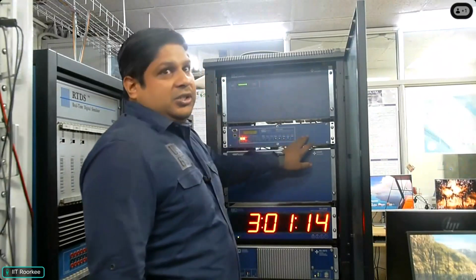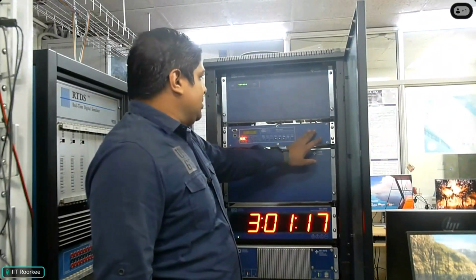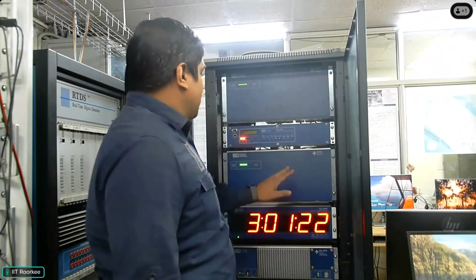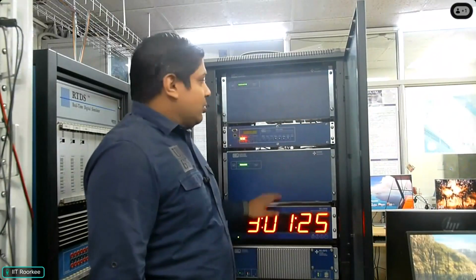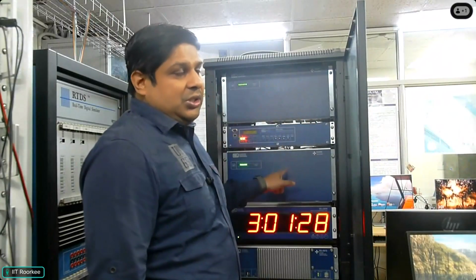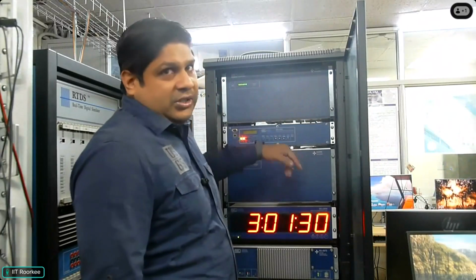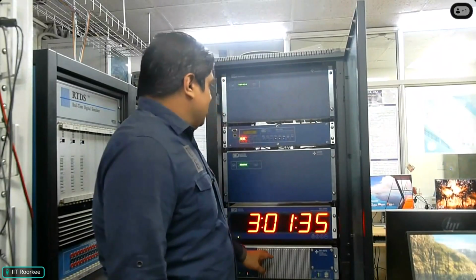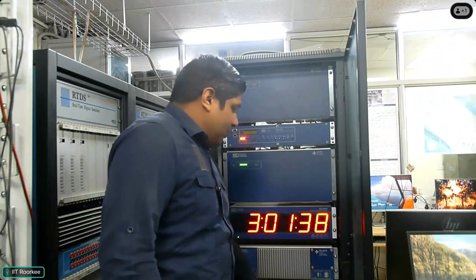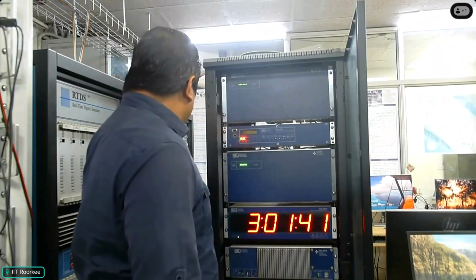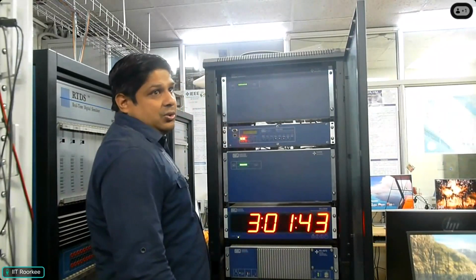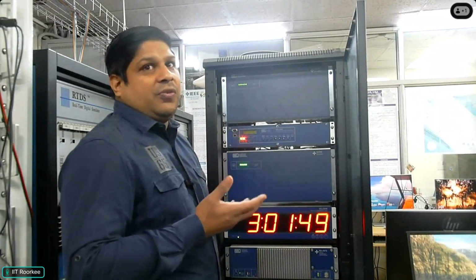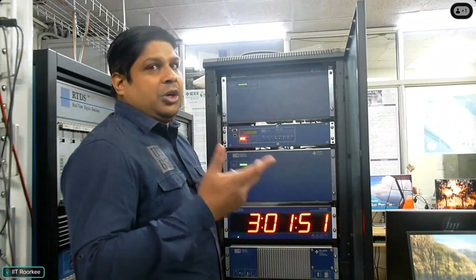And then this is a distance protection relay, a transmission protection relay. This SEL 311C. Most of the devices here are from SEL. And then this is the GPS clock. All these devices are time synchronized using the GPS clock. I will show you the connections at the backside when we go there. And this is the PDC. So all these PMU devices, 3 hardware PMUs here. And here we have a GTNet X2 card also. Using that card, we can have multiple software PMUs also, 8, 24 like that.